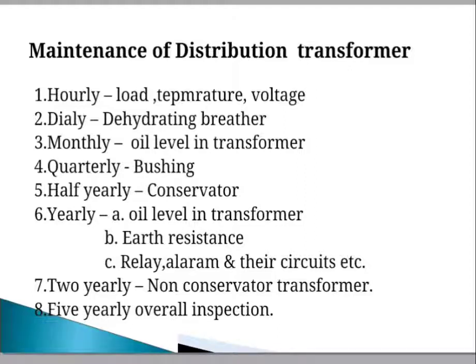Then we have to consider, first, the frequency of inspection. Suppose you consider the hourly basis. Then we have to inspect the load, temperature and voltage. We have to check the values of load, that is current, temperature and voltage against the rated figures, and if there is any rise in temperature, we have to start the fan if necessary.